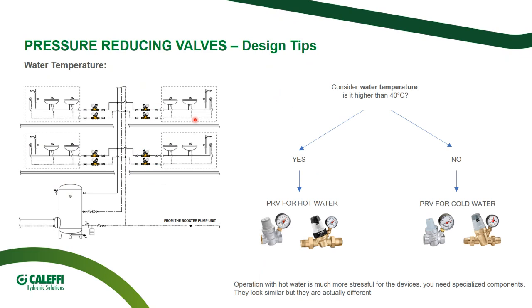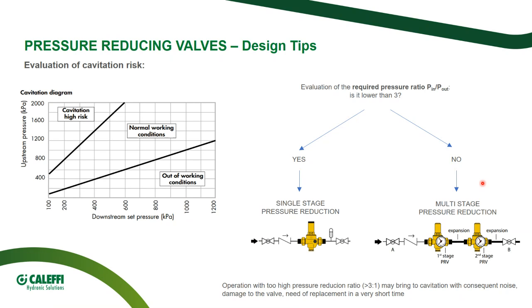So very quickly to the tips. First question. We have to consider the water temperature. Is it higher than 40 Celsius degrees? In case the reply is yes, we have to choose a hot water application PRV. In case it is no, we can stay with a cold water application line.